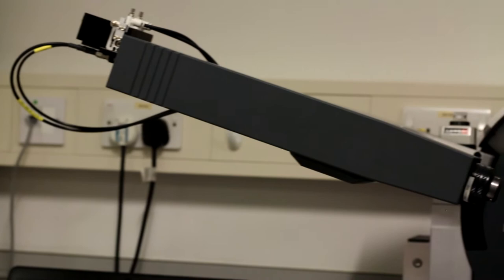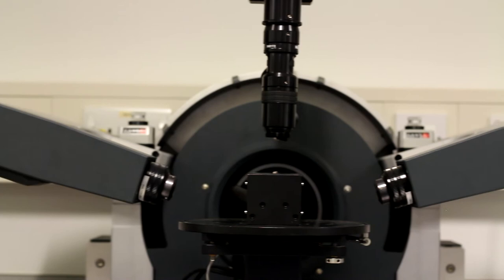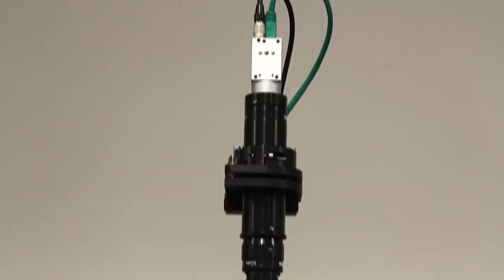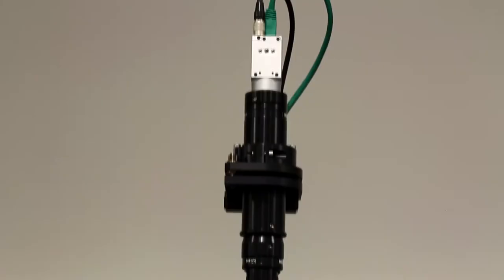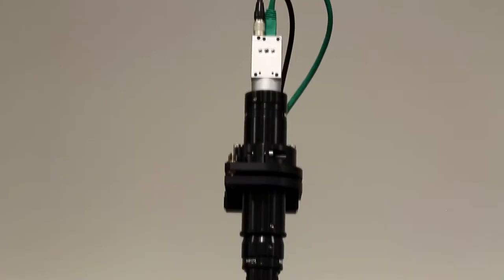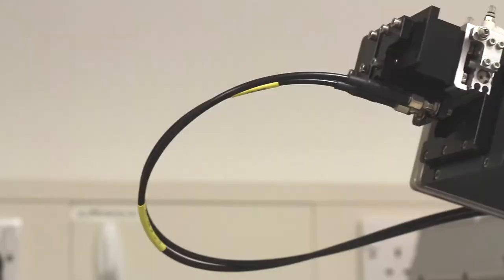Ellipsometry is a technique to measure the thickness and optical constants of a wide range of thin film materials. It utilizes elliptically polarized light that interacts with the material, causing change in phase and amplitude of the light. From this information we can then use mathematical models to calculate the thickness and the optical constants of the thin film.